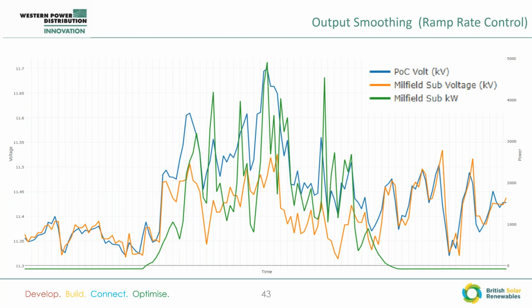This is another noisy graph, but what we're showing here is that the POC voltage and the Milfield sub voltage follow very similar patterns overnight, but that during the day the POC is significantly higher than the Milfield substation voltage when there's generation. So the green line is generation, and then you can see a large gap opening between the orange and blue lines there. So there's a large voltage drop over the feeder. And this shows that actually the ramp rate control would be best utilised at the POC rather than at the primary, because the POC is the place that's most likely to go outside of statutory volts and have the biggest swings, whereas the network itself at other parts can absorb it.